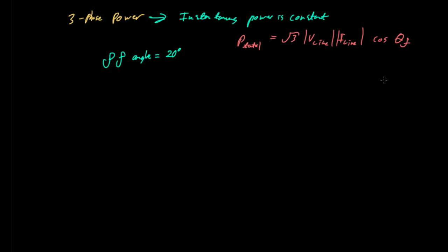So, fortunately, this is negative, which means we can use capacitors to achieve this. If that were positive, what are we going to have to add to the network to correct this? Inductors. Why is the power factor correction typically negative? That's not by chance. Most of the time we're adding capacitors. Why? What's causing this power factor disparity? Motors. Inductive devices, motors tend to be inductive. They're coils of wire. So most manufacturing plants or any kind of large installation appears as an inductive load because of all those motors. So we've got to add this minus 21.8 megavars of reactive power. We can divide that by 3 and get minus 7 megavars per capacitor.